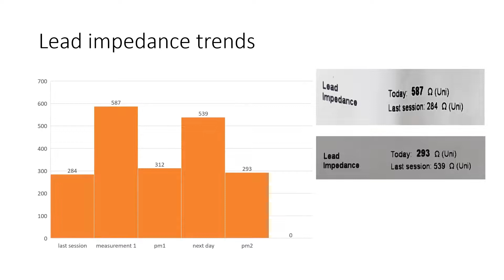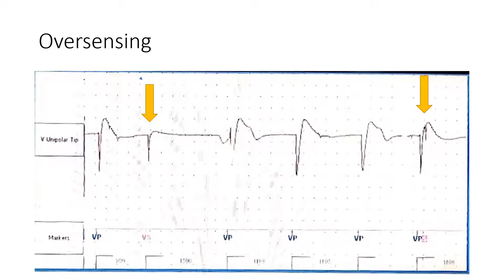During the time of provocative maneuvers, the lead showed presence of oversensing artifacts. These artifacts were intermittent, high frequency, non-cyclical, non-physiologic. As you can see, the intervals were in VF zone with post-pacing oversensing. There was a variability of amplitude, and these were reproducible by manipulating the region, thus giving us a diagnosis of lead fracture.